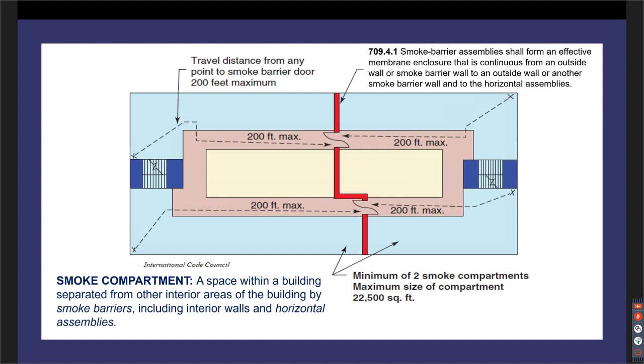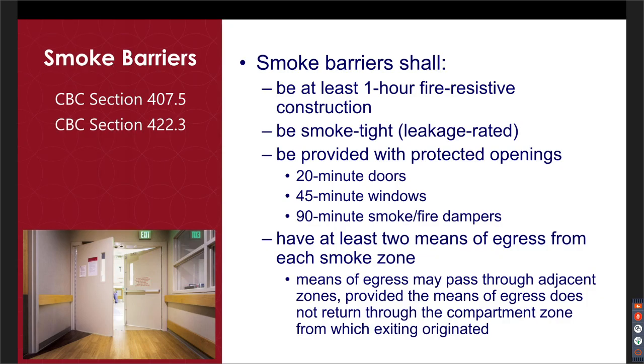Like for example, you need an L rating for different penetrations through smoke barriers. So it's going through that ceiling or that floor assembly that also makes part of that smoke compartment that would need to be protected with an L rating as well. And the big piece here too is that smoke barrier wall has to go from outside wall to outside wall or to another equally rated smoke barrier wall. Those walls have to be 1 hour fire resistive construction, of course, be smoke tight, hence the name. They're provided with protected openings, 20-minute doors, 45-minute windows, and 90-minute fire smoke dampers.